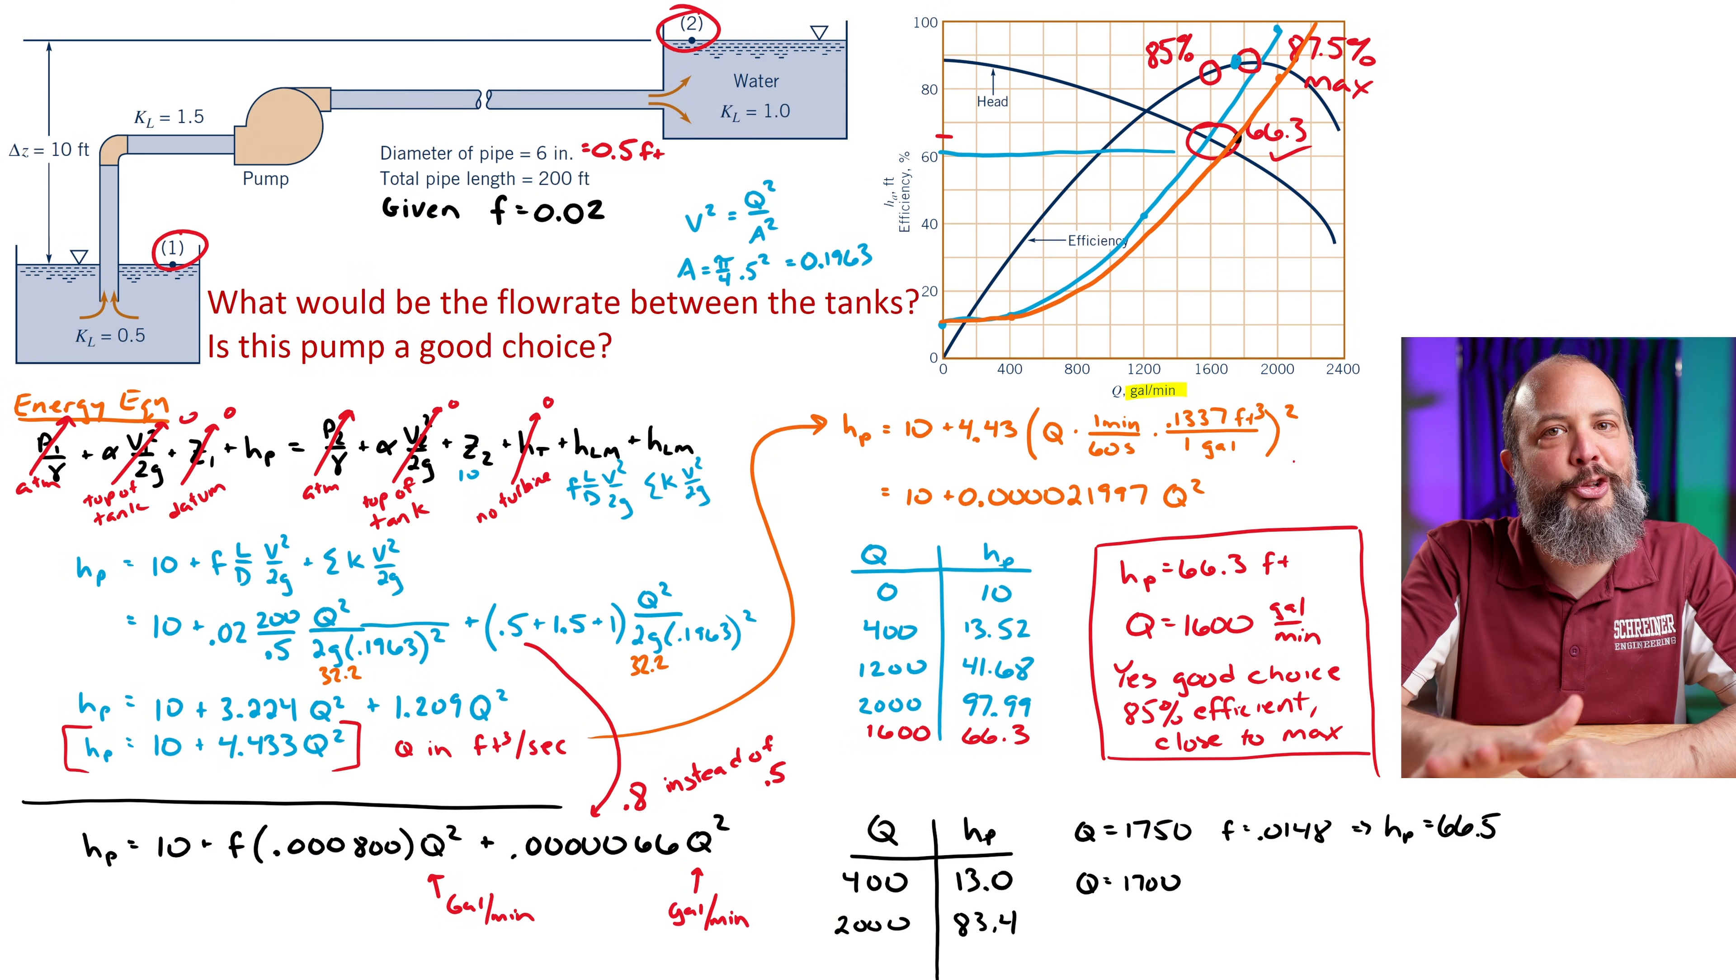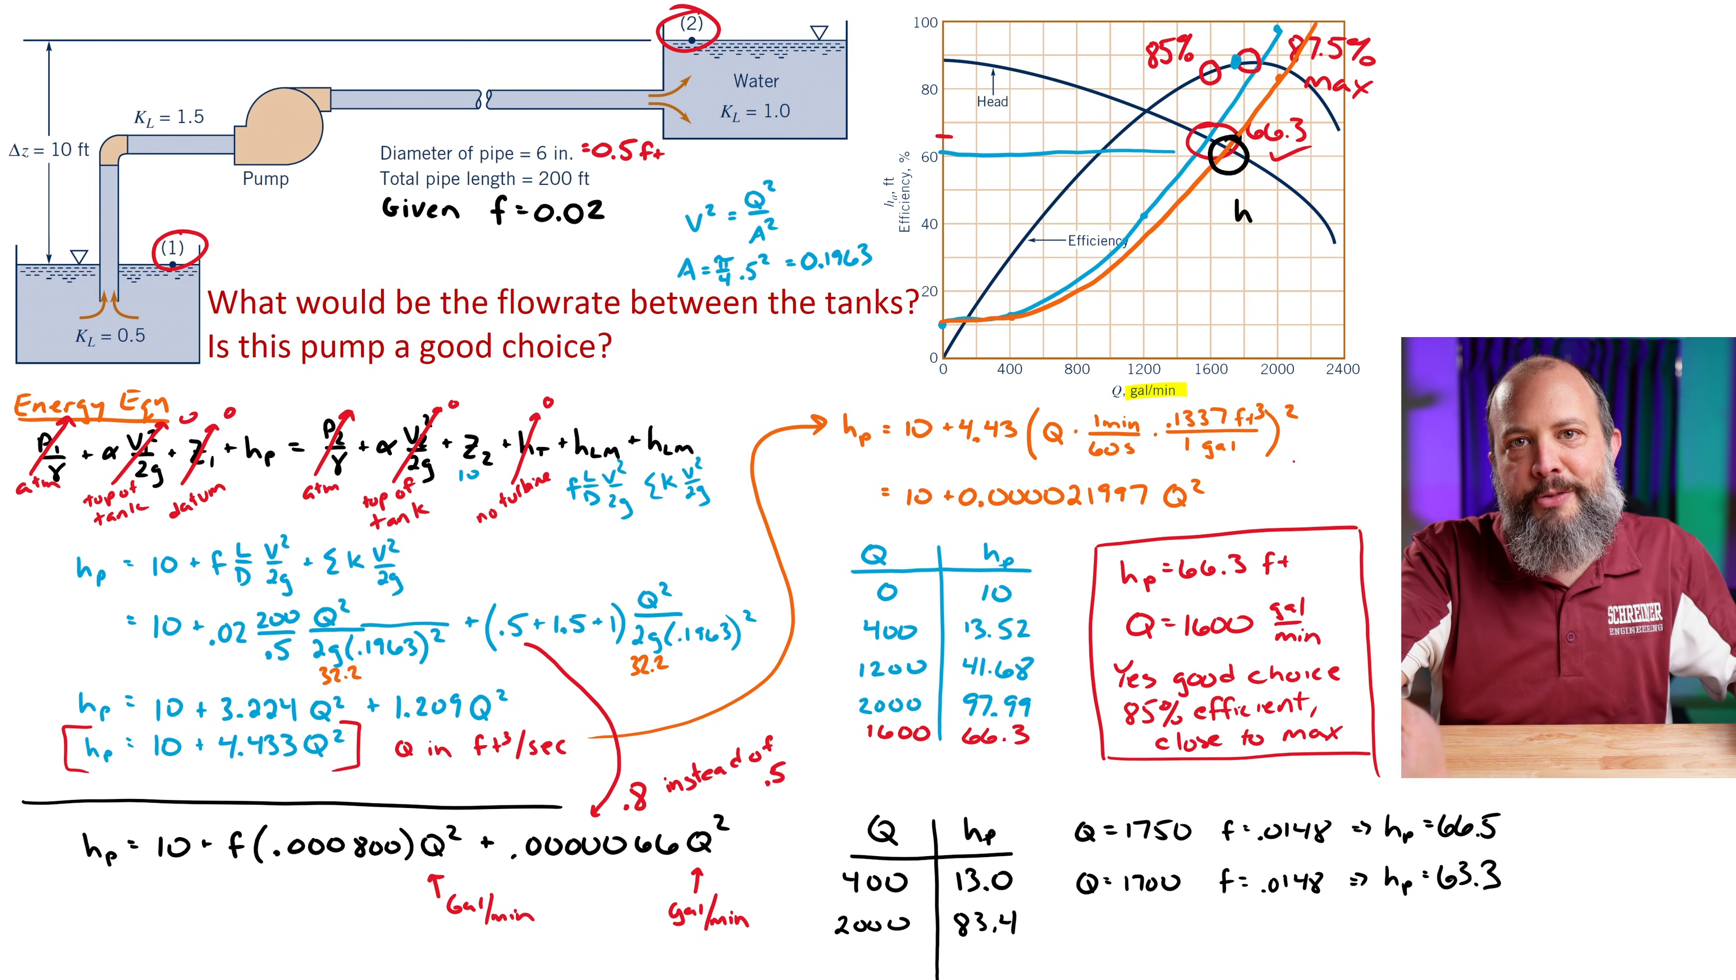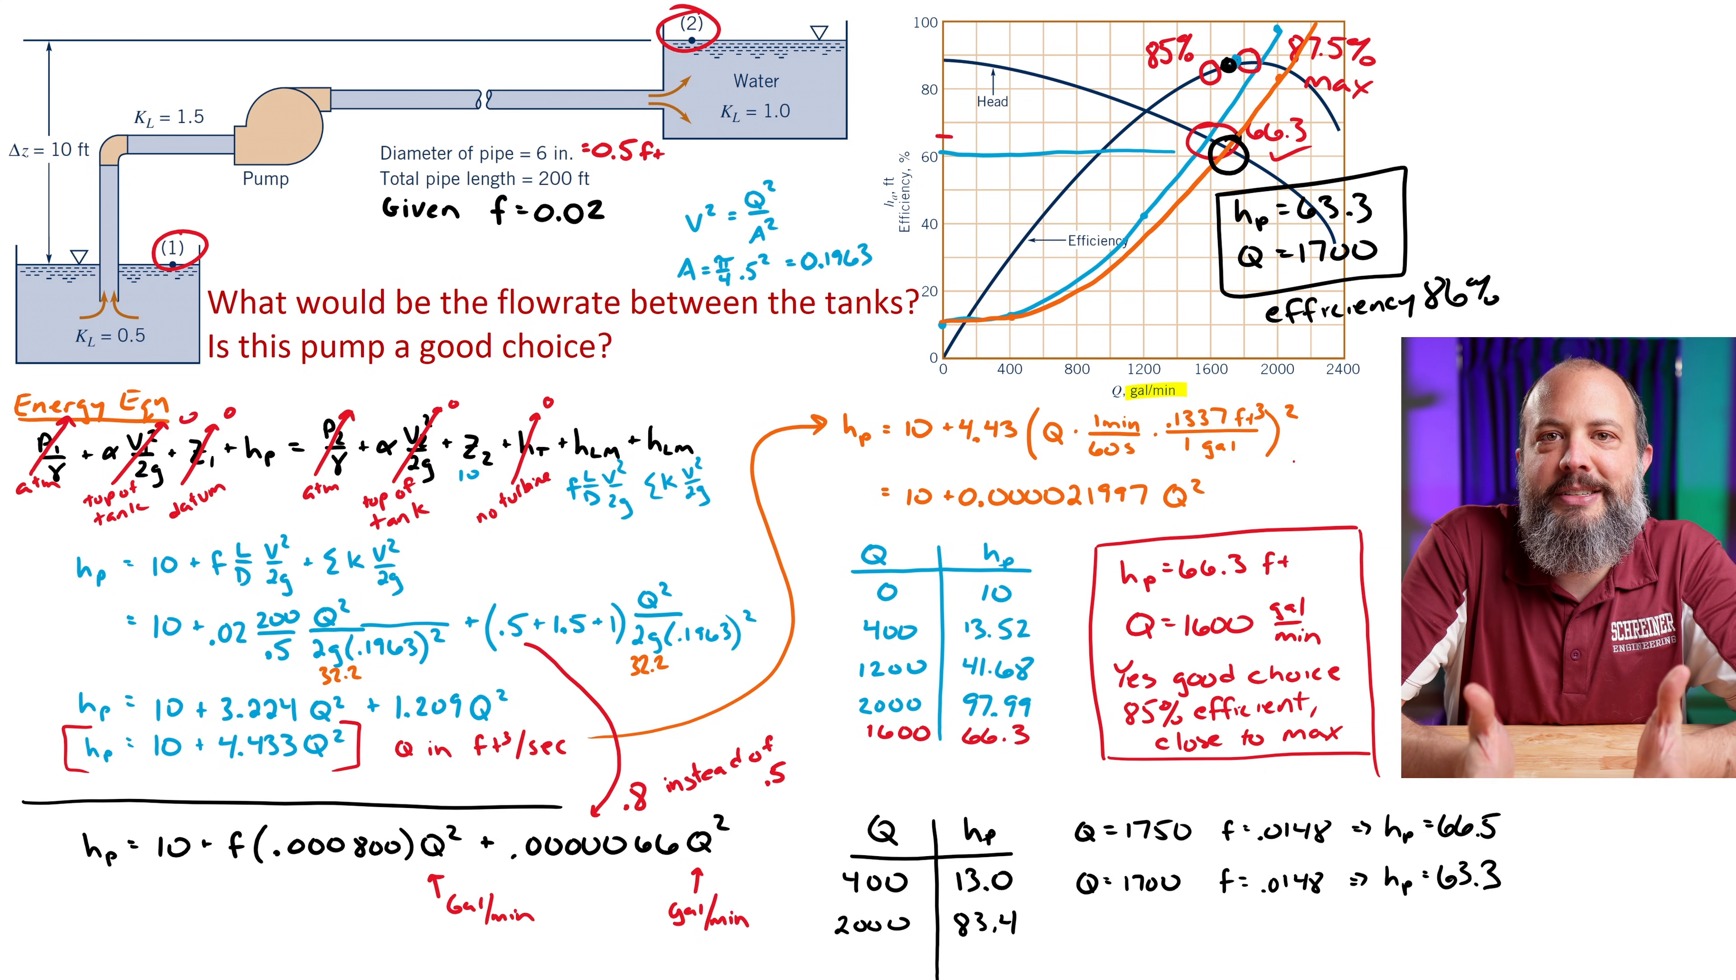And with the new line, it looks like it's actually closer to Q of 1700 gallons per minute. So if I use the same friction coefficient this time, it should be at a pump head of 63.3. And this looks like it does match the pump curve now. So in this new version of the problem where I come with my own friction loss coefficient and my own minor loss coefficients, I get a volumetric flow rate of 1700 gallons per minute, which is going to be even closer to maximum efficiency, probably closer to 86% this time. It's also still definitely a good choice of pump.